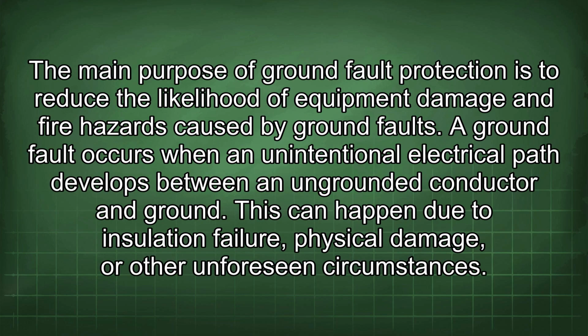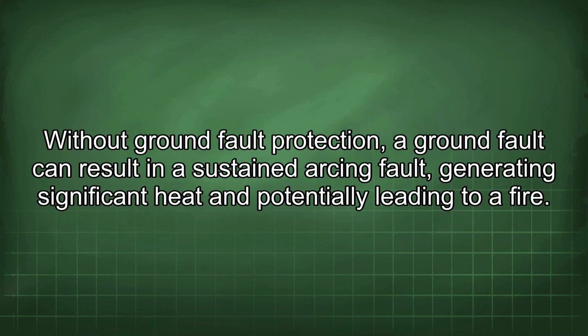The main purpose of ground fault protection is to reduce the likelihood of equipment damage and fire hazards caused by ground faults. A ground fault occurs when an unintentional electrical path develops between an ungrounded conductor and ground. This can happen due to insulation failure, physical damage, or other unforeseen circumstances.